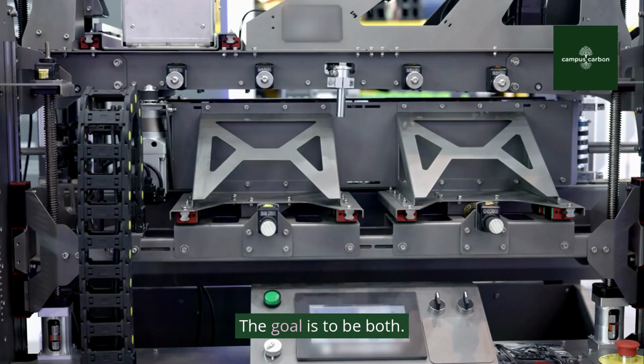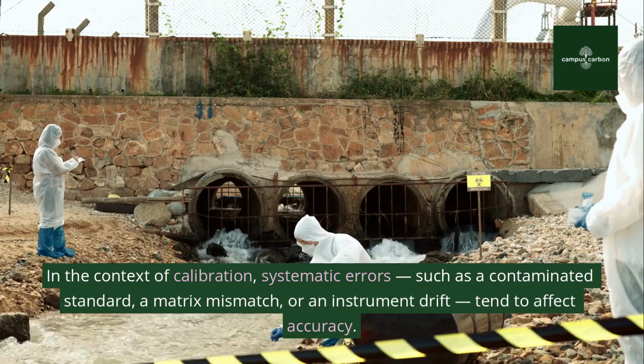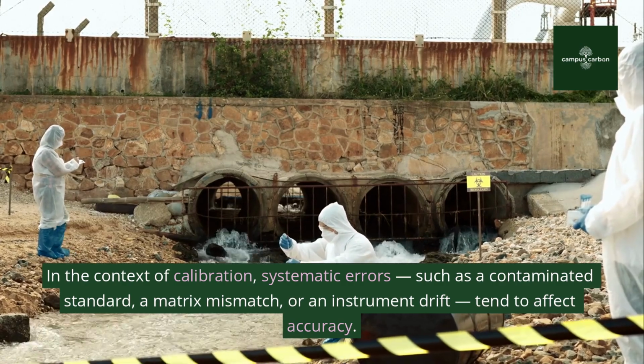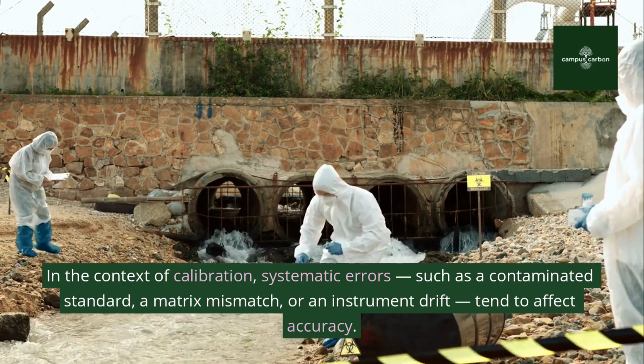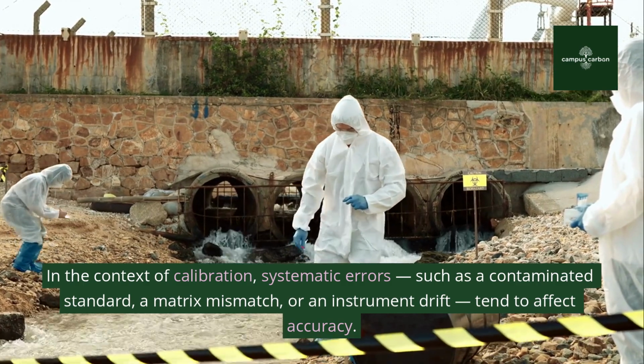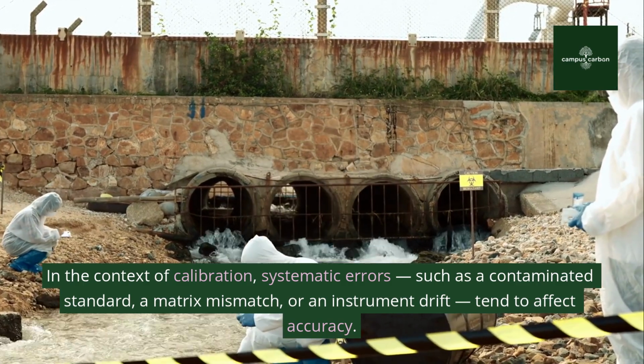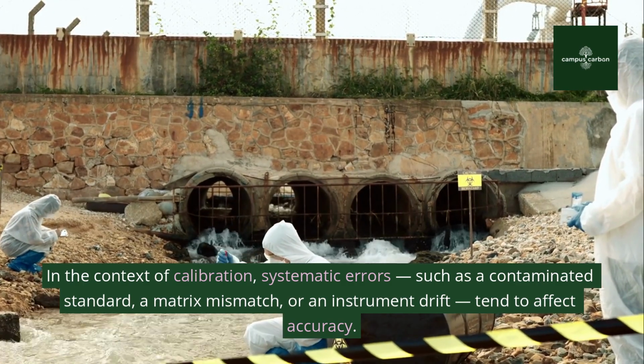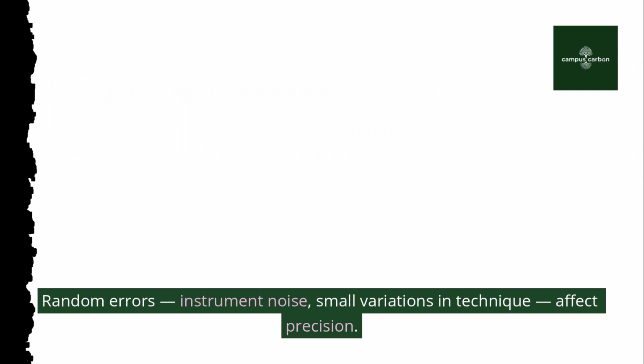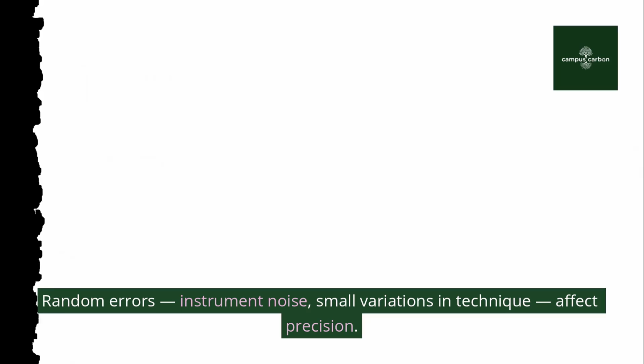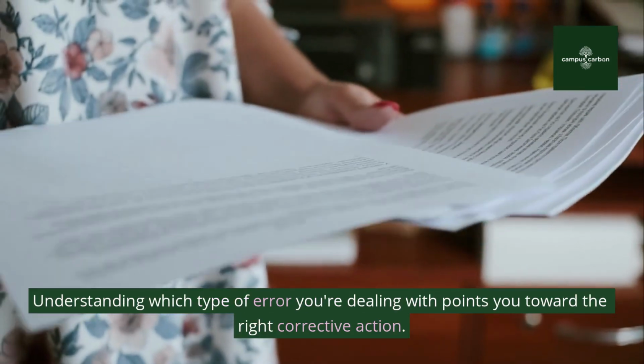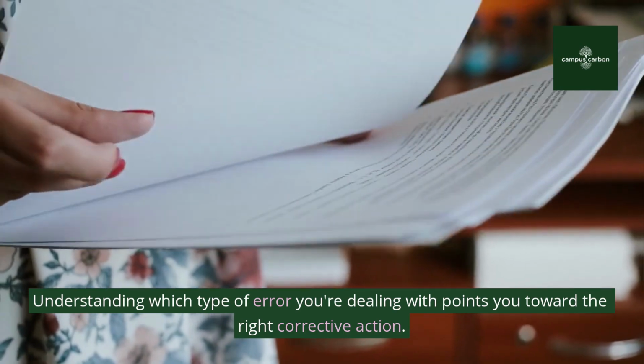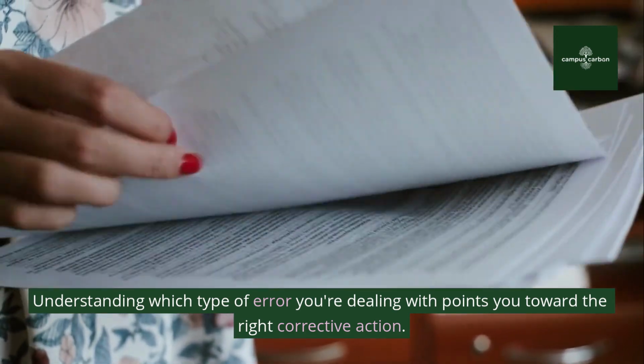The goal is to be both. In the context of calibration, systematic errors, such as a contaminated standard, a matrix mismatch, or an instrument drift, tend to affect accuracy. Random errors, instrument noise, small variations in technique, affect precision. Understanding which type of error you're dealing with points you toward the right corrective action.